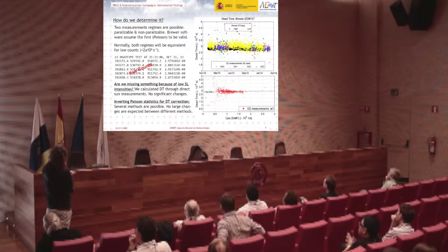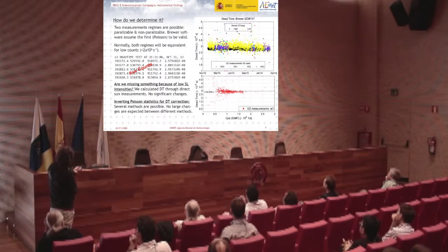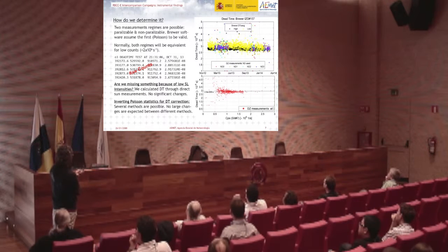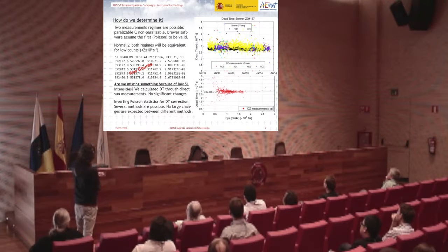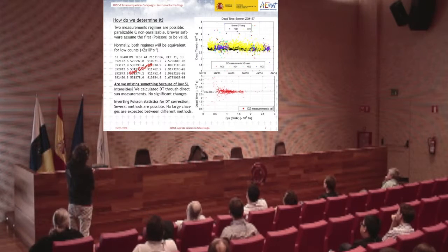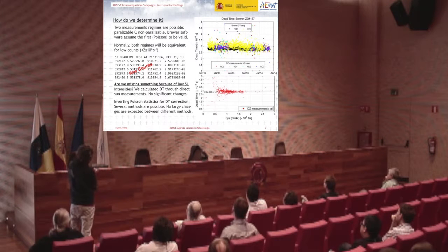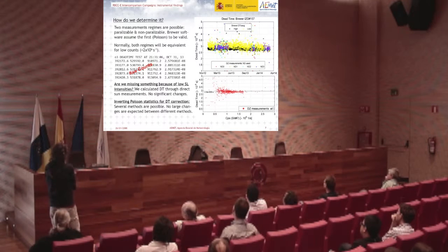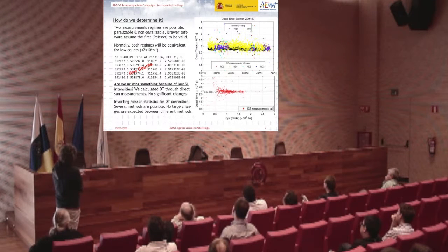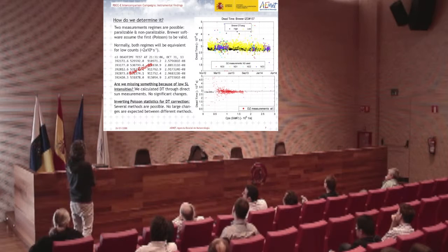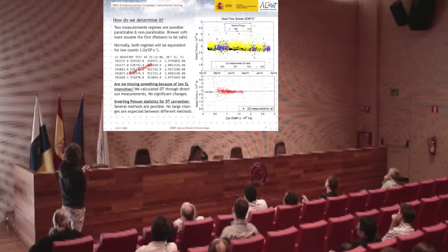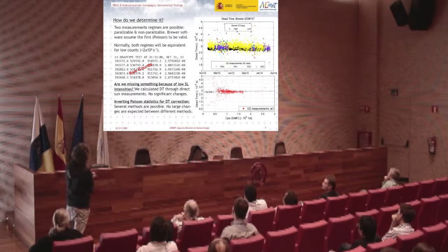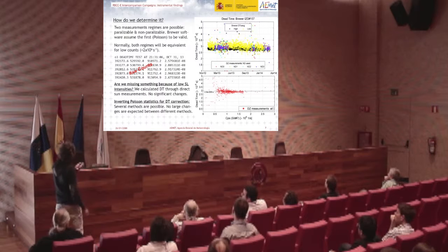And this is the dead time calculated versus time, and this is the same but versus intensity of light at the slit 7. So we see that the best results are for count regimes of about 1 million counts, and for low counts we have very noisy results, quite similar to the low intensity results of the standard lamp test, the dead time calculated with the standard lamp, I mean.